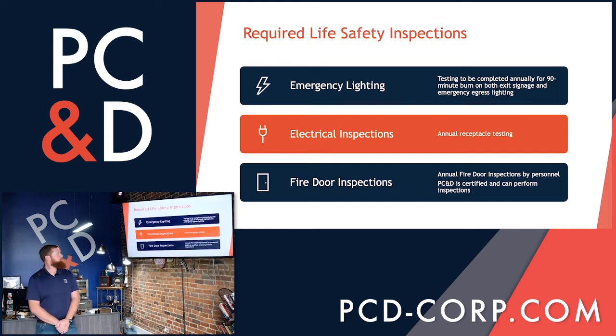All right, and so we'll touch briefly on these inspections listed. Your emergency lighting, as it'll be listed later on, you have a 30-second monthly and also a 90-minute burn, which is just known as a 90-minute burn. It's actually just a 90-minute test annually. So also you'd be looking at your electrical inspections, which would involve every single outlet in your building being tested annually. That would be for voltage, for tension, and also for the correct wiring. Polarity, thank you. The little tester you can pick up from Home Depot or Lowe's, your local hardware store, for maybe $20 will assist you in completing that. Once completed, document the room's okay. Obviously, if they fail, replace them or make necessary repairs and move on about your day.